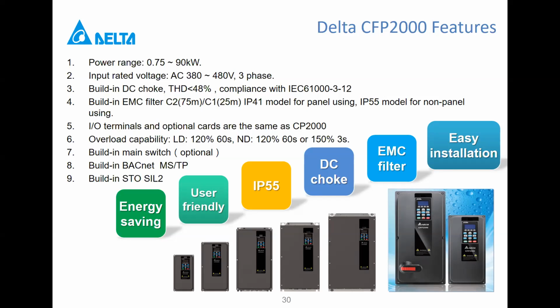For low duty, 120% up to 60 seconds overload. Normal duty, 120% at 60 seconds or 150% at 3 seconds. Built-in main switch for CFP, as I've mentioned.